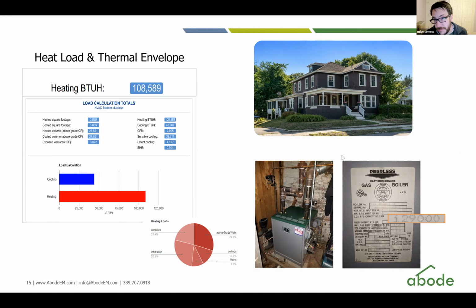So when I bought the home, one of the first things I did was an accurate heat load calculation. This heat load calculation is also referred to as a Manual J report. I put in all of the characteristics about my home, all the square footage, and measured all of the windows. It's a bit of work, but I'm glad that I did it because I ended up with a number of 108,000 BTUs per hour. What that means is, if it is the design temperature outside, which in Leominster is 2 degrees, I would need 108,000 BTUs every single hour to go from 2 degrees to 70 degrees. That's how much energy my home is losing through its walls, through its windows, through its ceiling.